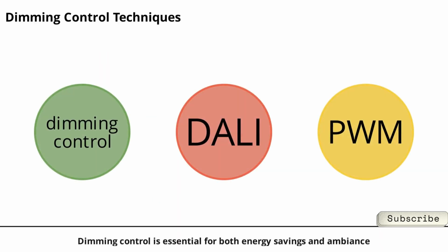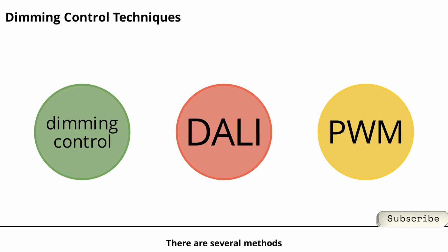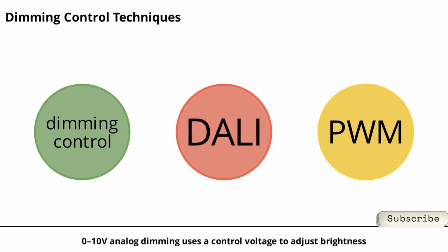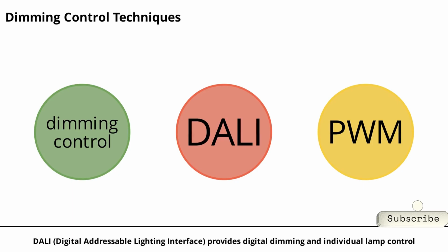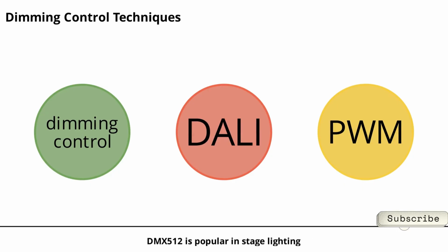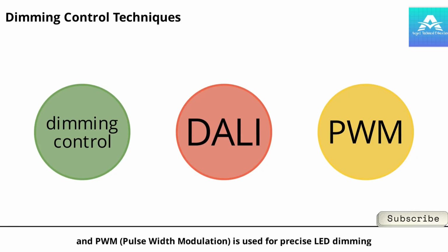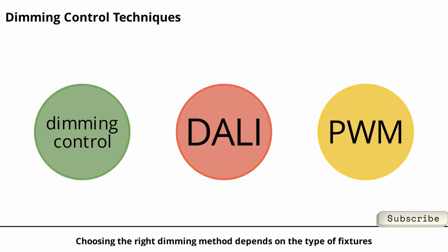Dimming control is essential for both energy savings and ambiance. There are several methods. 0-10V analog dimming uses a control voltage to adjust brightness. DALI, digital addressable lighting interface, provides digital dimming and individual lamp control. DMX 512 is popular in stage lighting. And PWM, pulse width modulation, is used for precise LED dimming. Choosing the right dimming method depends on the type of fixtures, desired control granularity, and integration needs with the BMS.